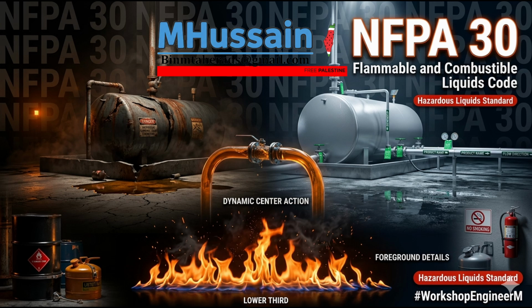A stray spark from routine maintenance happening well away from the actual tanks found the edge of that vapor pool. And the explosion propagated instantly back to the source. Total devastation. They had to completely rebuild the facility. And the redesign relied heavily on the mechanical ventilation standards in Chapters 10 and 17 of NFPA 30 to ensure continuous swept airflow across all those pooling areas. It's a stark reminder. You have to engineer your airflow, assuming the vapor is already there, just actively seeking a way out.